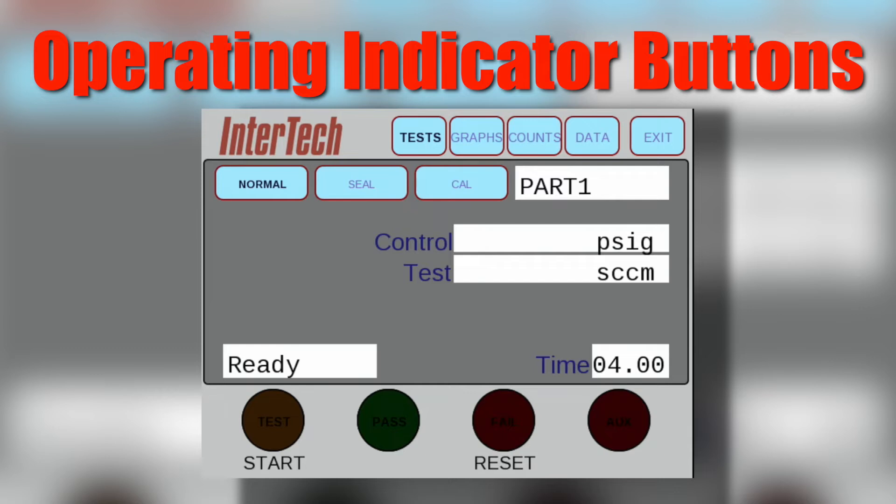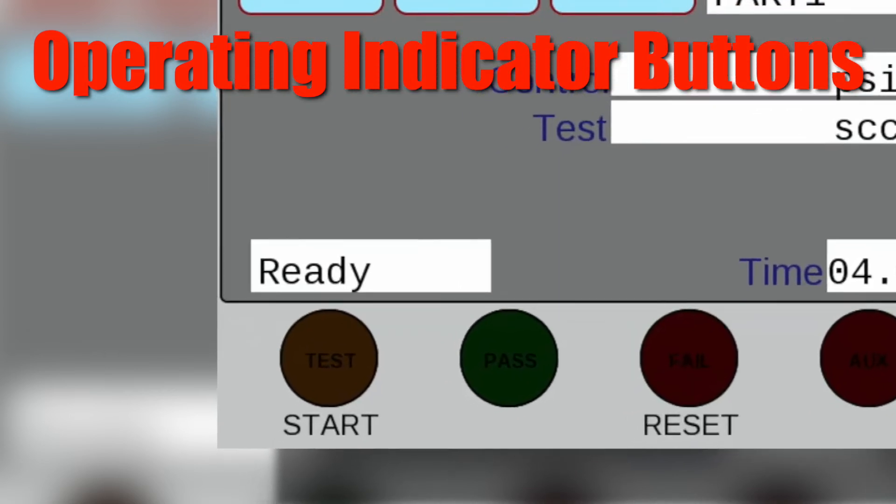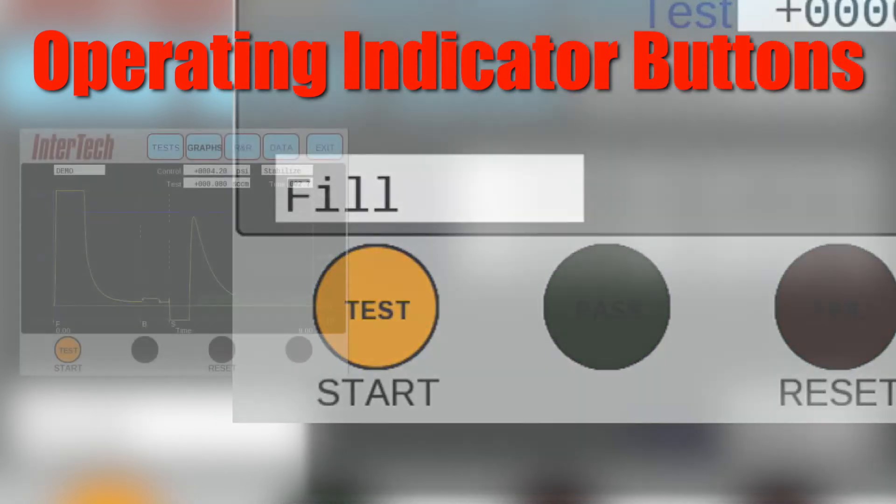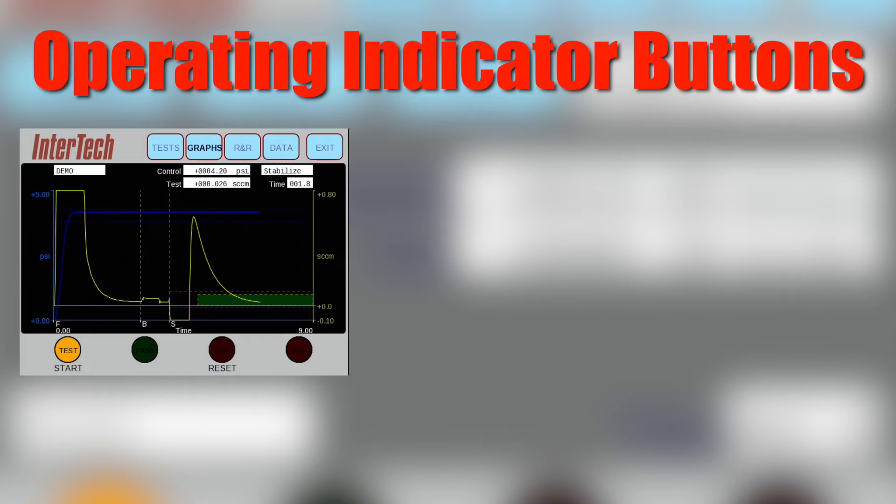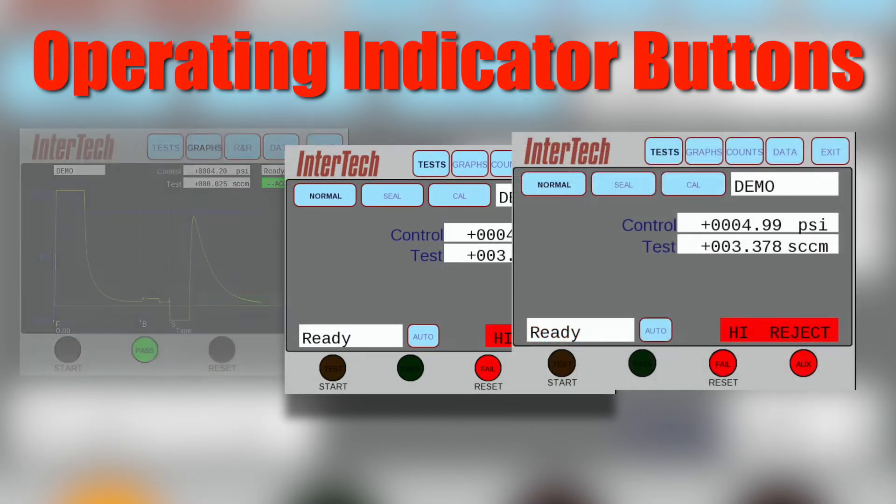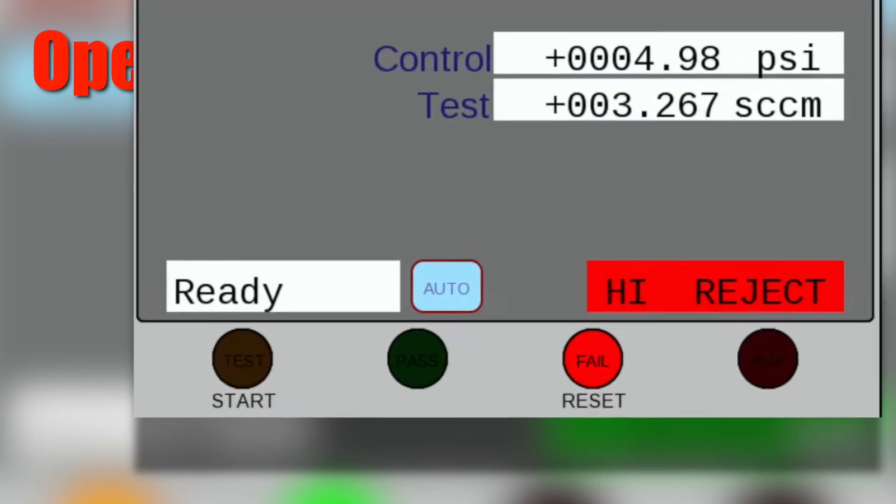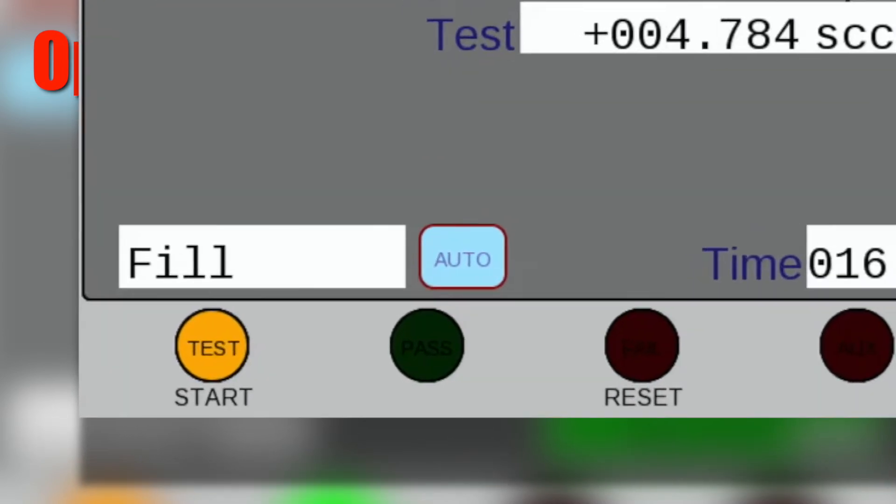The operating indicators on the bottom row include the start and reset buttons and show the test status when complete. Begin the test by touching the start button. A completed test displays accept, reject, or trouble indication. Using reset allows the operator to resume testing after a reject or trouble indication.